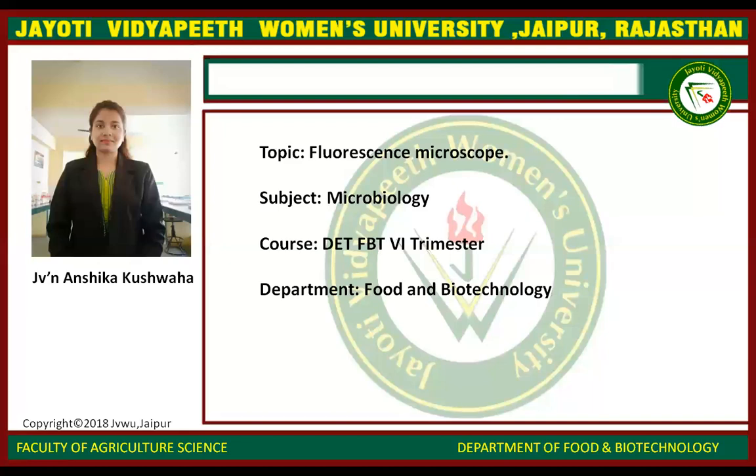So what is light source? Four main types of light source are used, including xenon arc lamps or mercury vapor lamps with an excitation filter, lasers and high power LEDs. Lasers are mostly used for complex fluorescence microscopy techniques, while xenon lamps, mercury lamps and LEDs with a dichroic excitation filter are most commonly used for wide field microscopy.